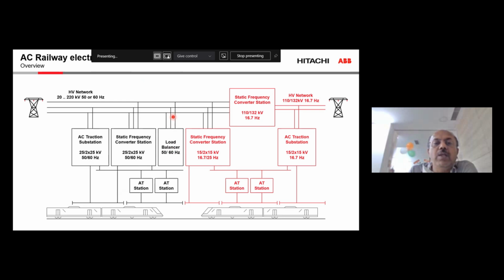This will basically compensate for the overall unbalance in the load, because when we connect two phases out of three, naturally you will have current through the two phases, but another phase is unconnected, and the current is zero related to the real power. In that sense, we can have the load balancer to balance out the negative sequence component generated due to this unbalance, and not only that, it will also compensate for the reactive power and balance the entire network we have connected.